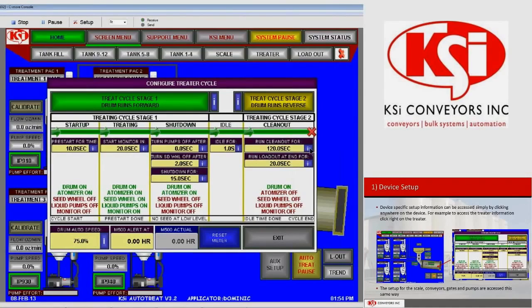And then after this time, after 120 seconds, we're going to run our loadout conveyor for an additional 20 seconds, or 40 seconds, or 10 seconds, whatever that might be. And then after this 20 seconds, the drum's going to turn off, and the conveyor's going to turn off, and your treater's going to shut down.